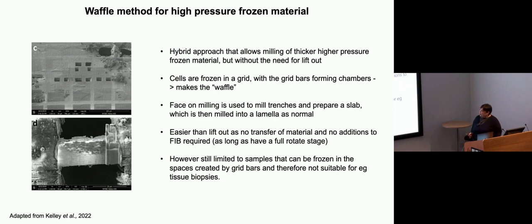Because it's already on a grid, it's in a situation that can be taken to the microscope, so no lift-out is needed. This makes this quite attractive and also is nice because you don't need any special equipment as long as your FIB has a stage that can do full rotation, which most of the newer instruments do. You don't need the lift-out needles. The idea is that you've got these thick waffles, you mill the trenches, similar to how it's done for lift-out, but instead of making the few micron lamella, it's just to prepare these areas.